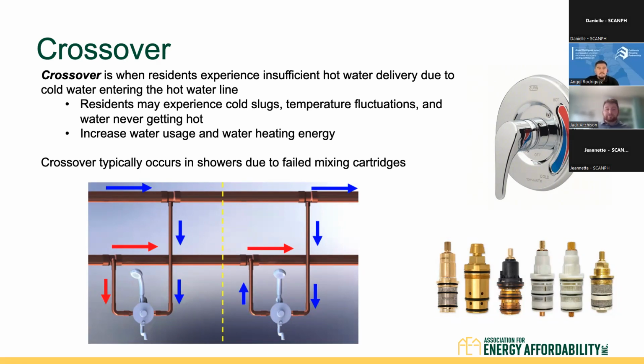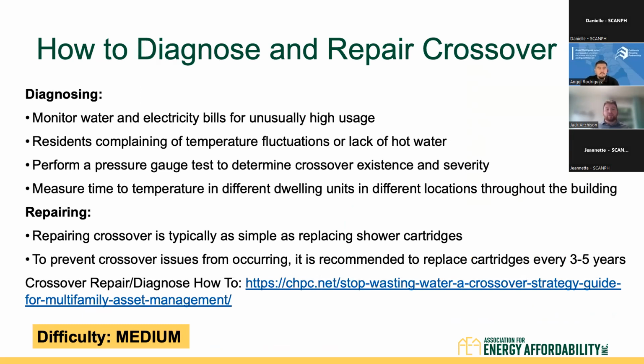Next slide, please. So how to diagnose and repair crossover. Diagnosing: monitor water and electricity bills for unusually high usage. That can indicate a crossover issue, because when people are using more water, they're also using more hot water, and your water heater has to work more frequently to recover that load. As that cold water distributes throughout the building, if it comes back through the return line to the water heater, the water heater has to reheat that water, and that increases your load.